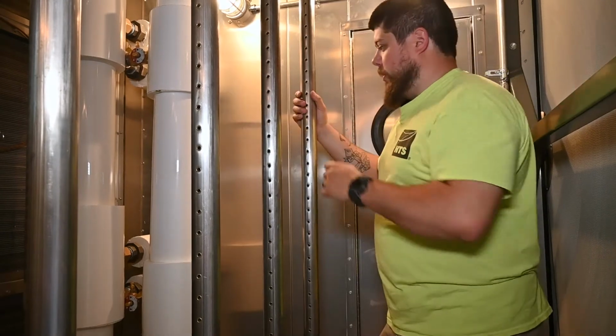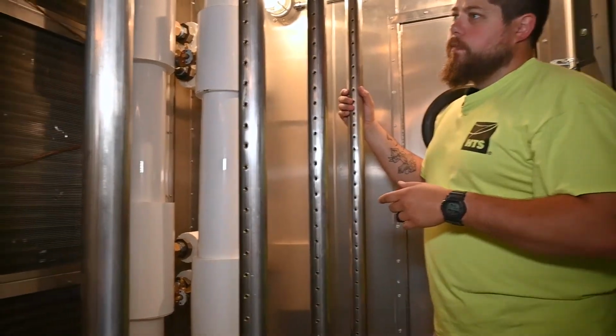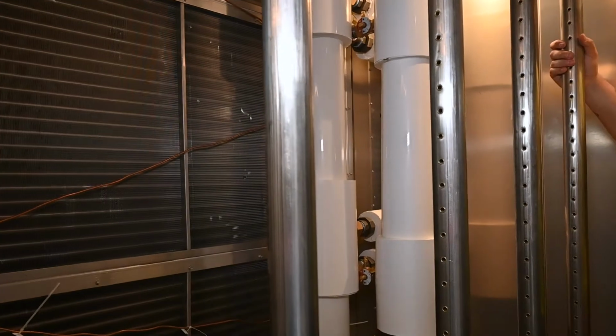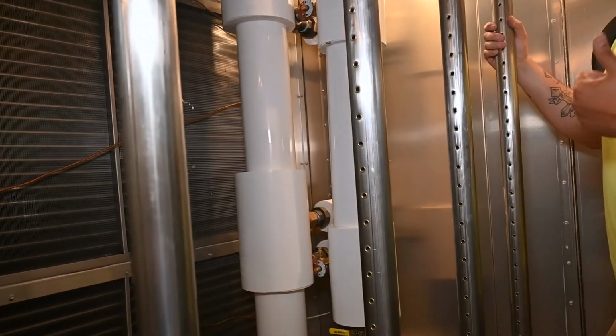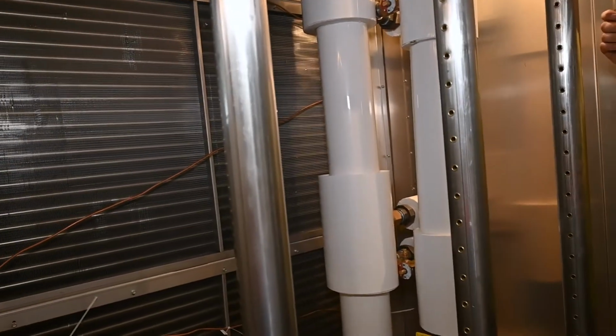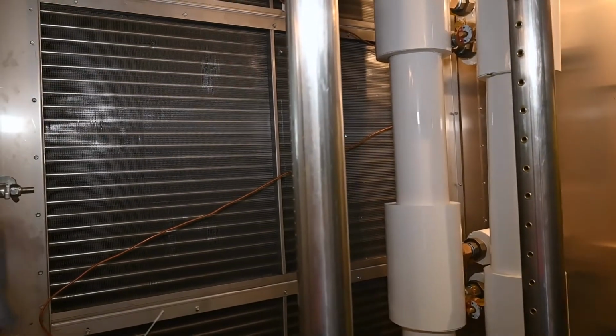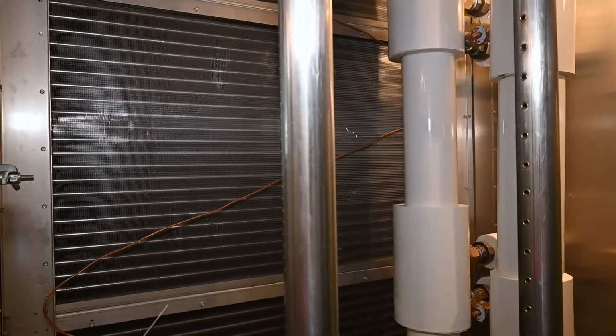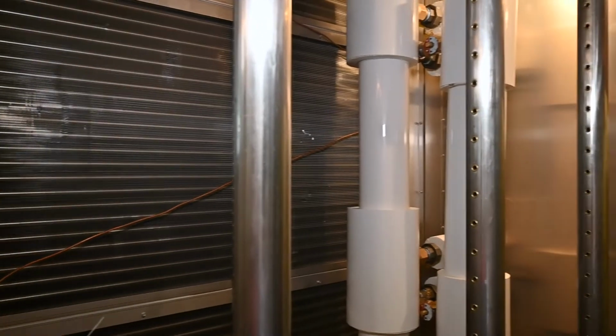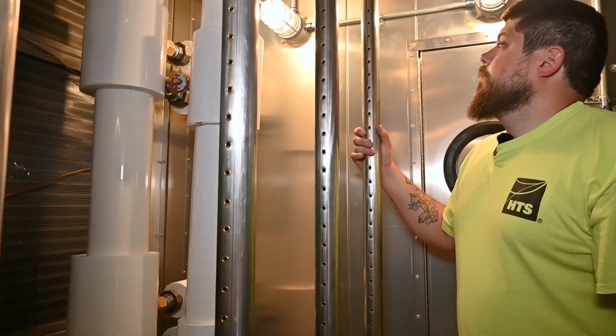Right up against here, I believe we have our heating coil. Just like I had mentioned with the cooling coil and the rest of the coils, they can be cleaned with water if they need to be. Ideally, if filters are maintained, you should never have to worry about the coils and clean anything with them. And that should be good for this section.